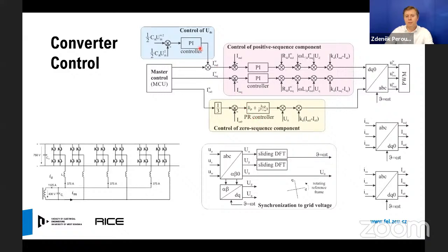We have two master control loops. The first one is the control of the DC link of our converter, which commands the active component of the positive sequence current. The second master control is responsible for the generation of the reactive component of the positive sequence current in case the STATCOM functionality is demanded. And this master control is also responsible for the generation of the compensation current command.